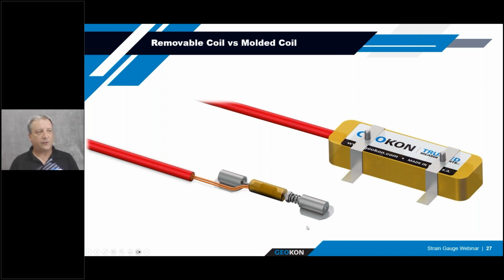The other model is the 4150 shown here on the left. That one has the coil assembly wrapped around the wire tube already, that comes from the factory that way, and then you've got the small leads coming out that transition into the regular signal cable. The benefit of one versus the other, time-wise, it might take less time to install the 4000 with the cover already installed, but sometimes there's alignment issues with getting this cover positioned correctly over the wire tube, and you may not get the readings all the time. More often than not, it works very effectively, but sometimes we've had issues where they didn't quite get lined up correctly, and so there was problems with the readings occurring. This one, the 4150, takes a little bit more time and finesse, but as with any good project, the more time you spend on it, sometimes the better results you get.